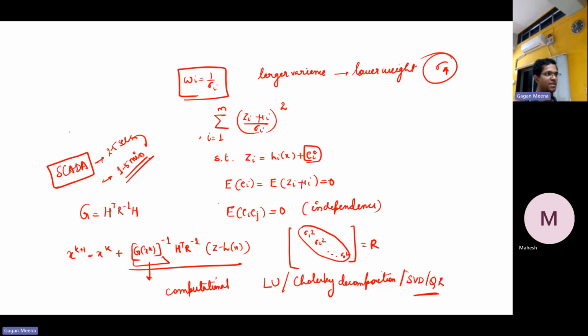It is very difficult to obtain the voltage phase angle in real time from these dispersed locations by using conventional measurements and the state estimator. Therefore, real-time visualization is not possible by using SCADA. Because of all these problems, the PMU was brought in, which provides measurements at a sub-second rate. We have 50 to 60 samples per second. They also provide direct measurement of the phase angle, which was not possible with SCADA. Now PMU can be integrated into the state estimator, and that also makes the state estimator linear.